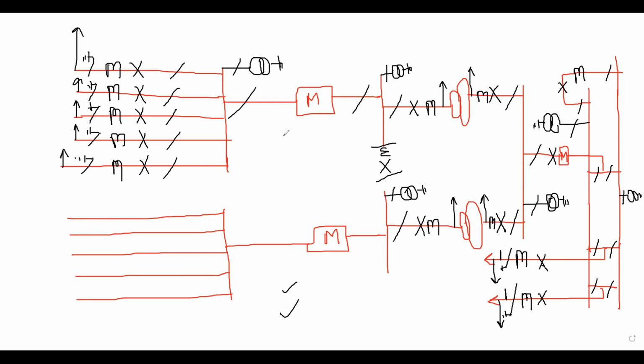And suppose if this project has communication, we have communication from substation to substation. Suppose a fault occurred in my substation, and I want to tell the connected substation there is a fault in my substation. Could you please open up the breakers? So there should be some communication between the two stations. If you are adopting this communication, it can be done with two types of communications. One is PLCC, power line carrier communication. The other one is fiber optic telecommunication, FOTE cable through OPGW wires. Two types of communications are there. In the old projects, we have PLCC, which is power line carrier communication.